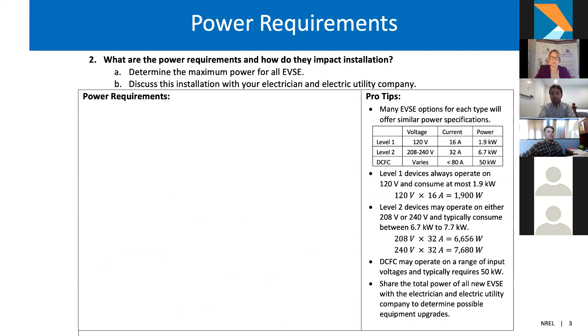Realize you're receiving 120/240 volts, like a typical residential location. That limits what voltage you'll use for a Level 2. A 32 amp system is pretty common for a lot of EVSE, and a 40 amp breaker sizing is very common, giving you about 7.7 kilowatts. Then you size up your total peak power. Worst case, if all are plugged in, you'd get a little over 45 kilowatts at peak. That's something you can communicate with your utility company when installing new stations, the worst case new load.